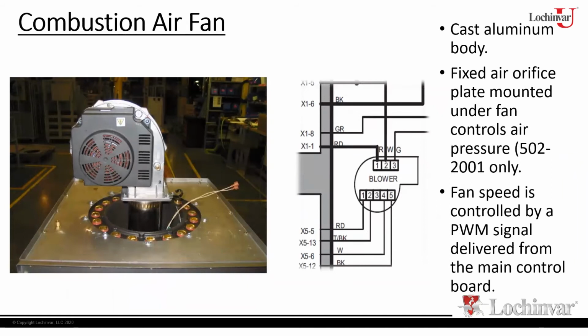So how does this start? It starts with the blower. All right. Every unit's going to have a modulating fan on it. Depending upon the size of the heater will dictate the size of the fan. Now the fan itself will have two connections. Again, a power connection, which could be either 120, 208, 240, 480, depending upon the size of the product that we're dealing with. And then we have what's referred to as the PWM signal, or the pulse width modulation signal, which is what's actually controlling the fan. And that PWM signal is telling the fan when to start, when to stop, where to modulate to. It's controlling the operation of the fan itself.